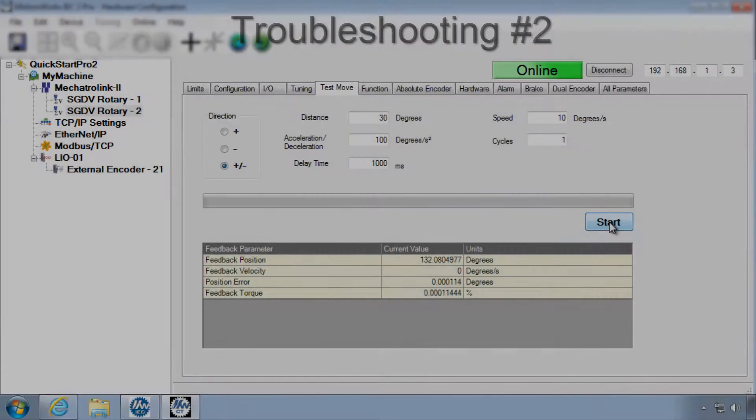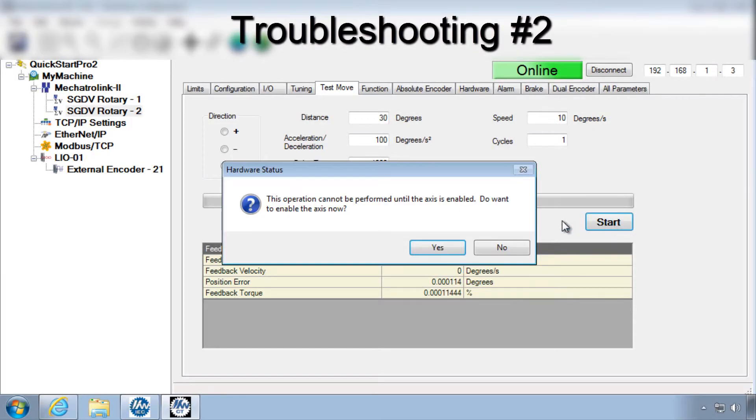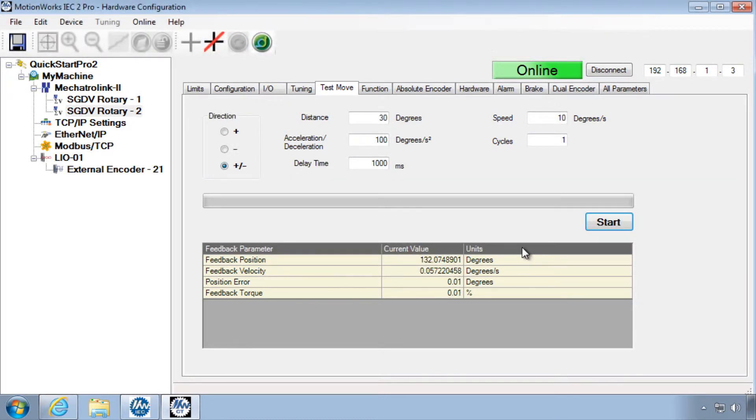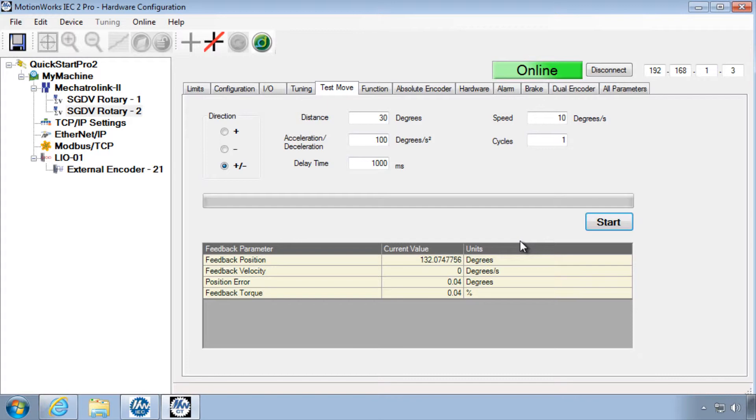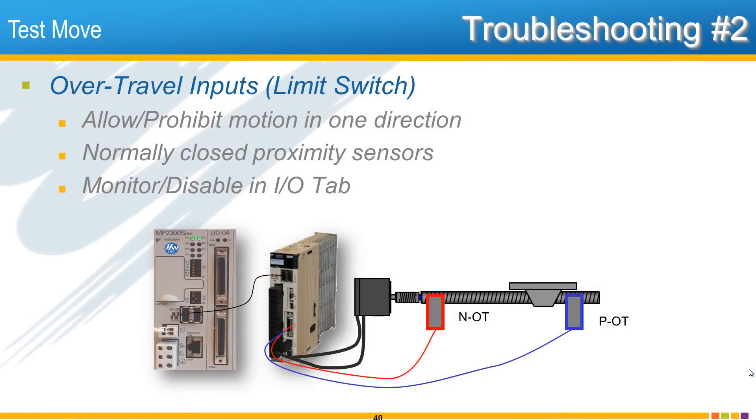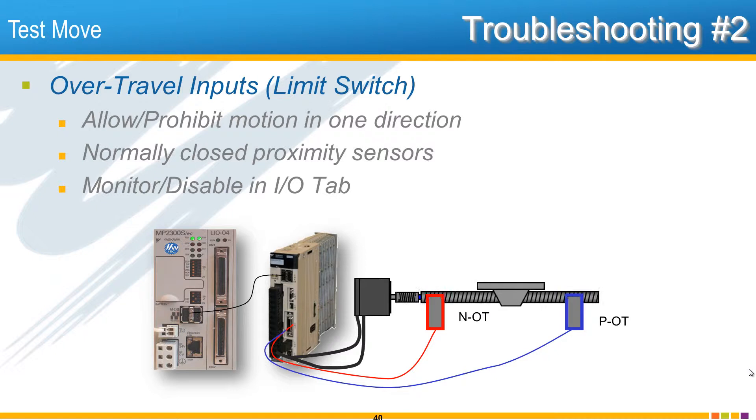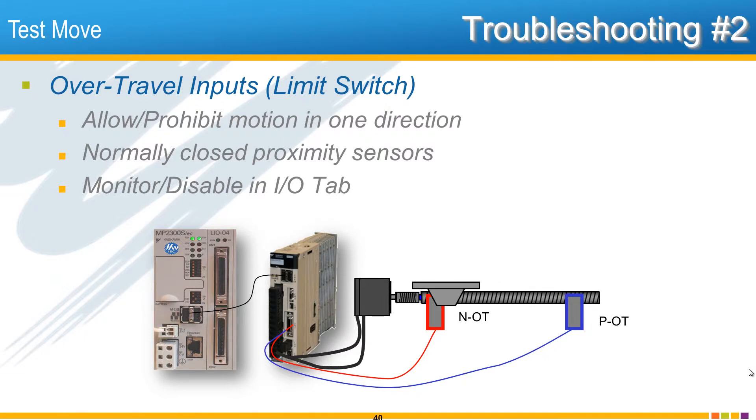If when you click start the axis enables but it just doesn't move, the most likely cause is the over travel condition, otherwise known as limit switches. Over travel is not an alarm, but they are digital inputs that allow or prohibit positive and negative motion. The over travel inputs by default are to be connected to normally closed proximity sensors at the end of a linear actuator in order to stop that load from reaching the mechanical limit.